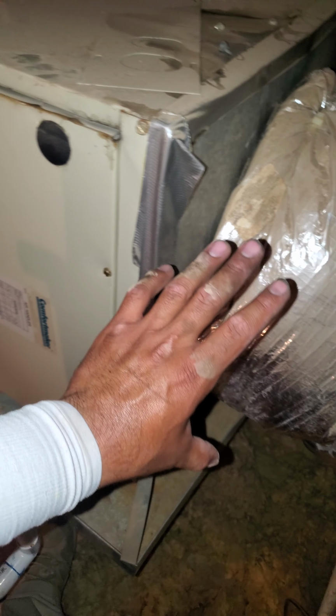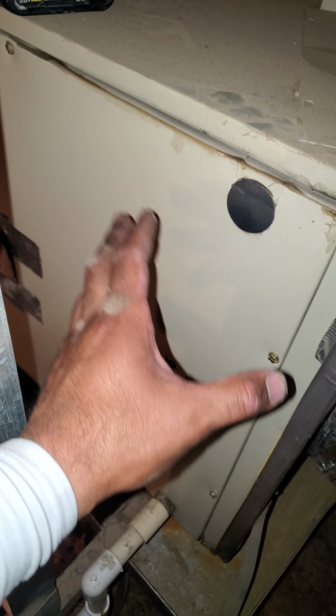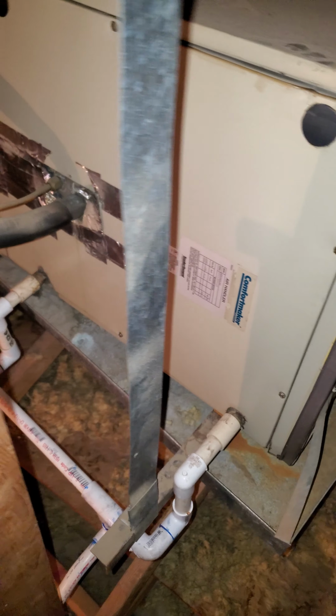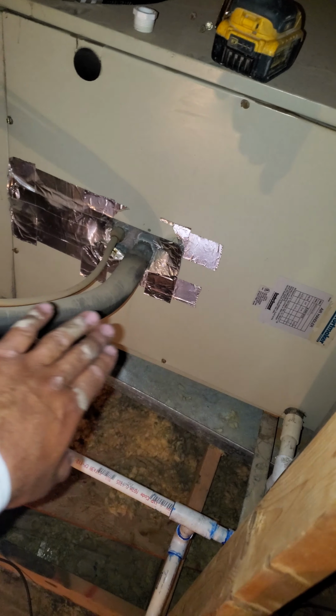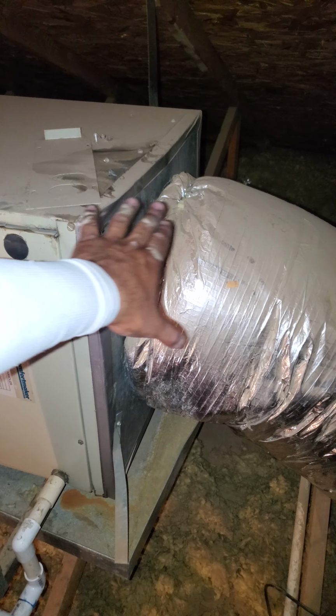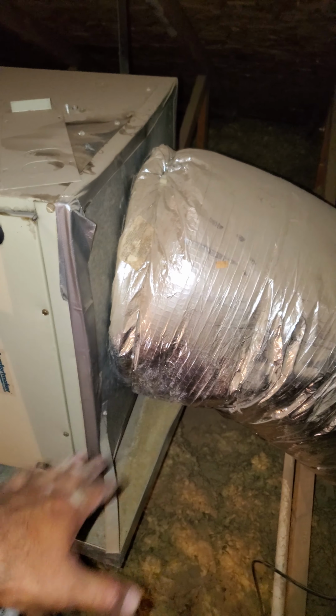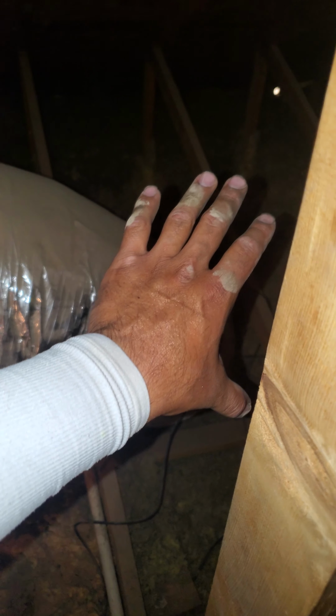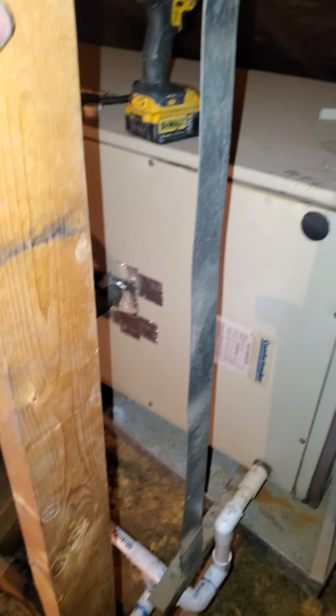It's only going to go in a straight line, and by the time it finally expands into the cabinet, it may already be halfway through this cabinet, this coil. If you install, like we are going to with the new one, a big piece of ductwork in the back, square metal ductwork, and attach this to it, then it will expand in that ductwork, and by the time it starts to go through this coil, it will go pretty much flush evenly through the entire coil and get your maximum amount of cooling out of that coil.